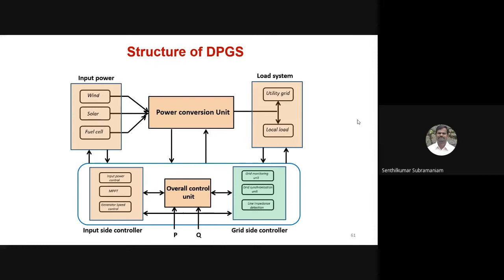When you are considering the input side controller, it is the input power controller, MPPT, or the generator speed controller in the case of a wind energy conversion system. So the overall control unit is indicated with real and reactive power control. When you are coming to the grid, how smartly you are feeding power to the grid and what controls are required? Grid monitoring, grid synchronization, line impedance detection, like this.